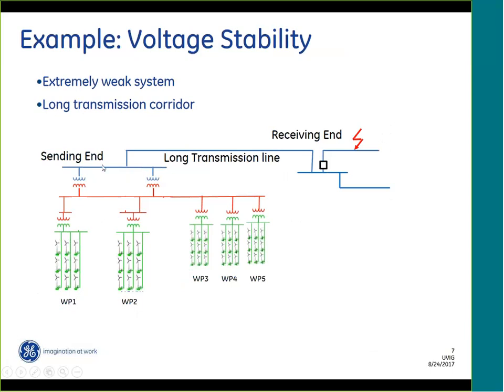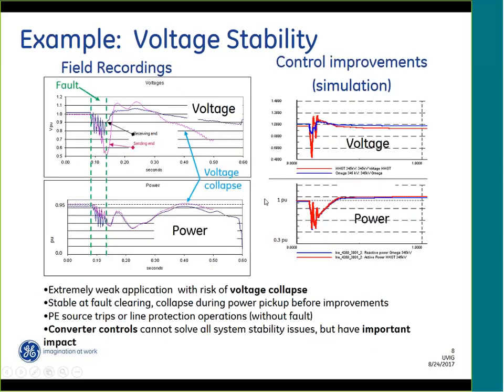I'm going to use the wording sending end and receiving end to refer to the different quantities here in the next slide. So then here we don't have an SVC. We have several wind plants, and we're going to look at the voltage stability challenge. So on the left here, we have some field recordings. On the right, some simulations. I would refer to the field recordings because those show a concrete stability issue that then was resolved.